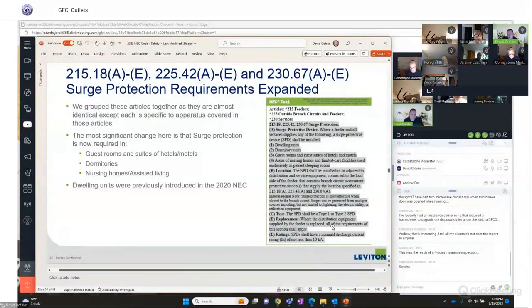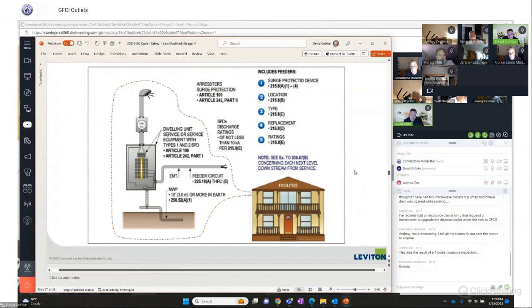The other thing that came into the 2020 code, which is now required on new homes, is surge protection. So we talked about GFCI protection, personal protection, AFCI, personal protection. Surge is another thing to really protect equipment and appliances in your home. So the code basically says if you build a house, it must have whole home surge built into it. This is showing a diagram of your power coming in, and basically saying after you get past this point, you need to start introducing surge protection. They really want whole home surge is what the code inspectors are looking for.